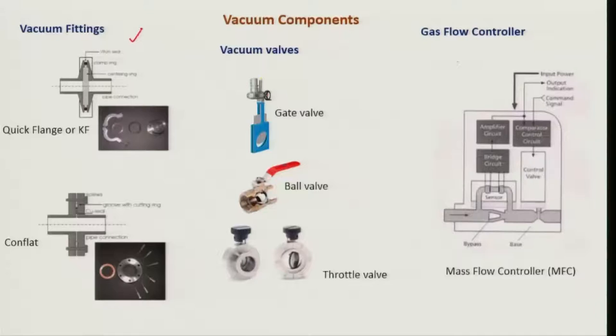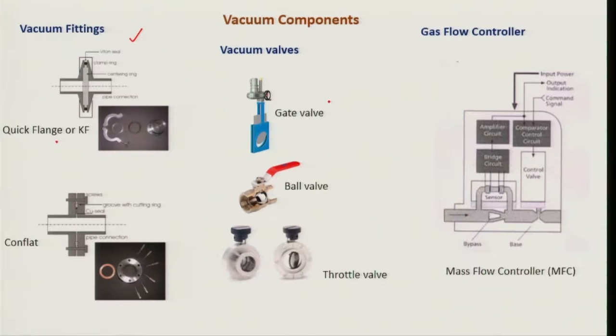Apart from pumps, there are several other components that are part of a vacuum system, such as vacuum fittings, which should be leak-proof — for example quick-flange or conflat fittings. Vacuum valves allow you to control pressure pneumatically, by computer, or manually. When you need to flow a pure gas into the system, you can use a mass flow controller to introduce the gas at a controlled rate. These are all part of a vacuum system.